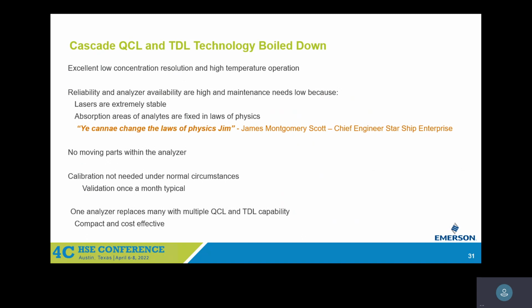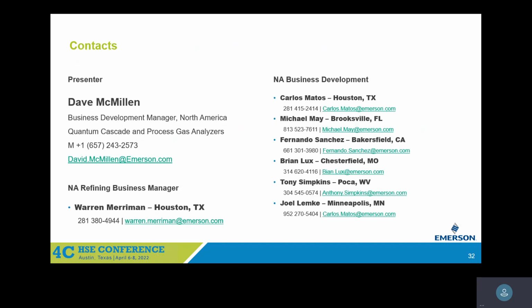So boiling this down, we get excellent resolution and high temperature operation, very, very reliable. Because lasers are extremely stable. Absorption areas of the analytes are fixed in the laws of physics. I mean, it's physics. No moving parts within the analyzer. Calibration typically isn't needed under normal circumstances. And we are able to do a lot of measurements with one cost effective analyzer. So, we've been having some good success with that.